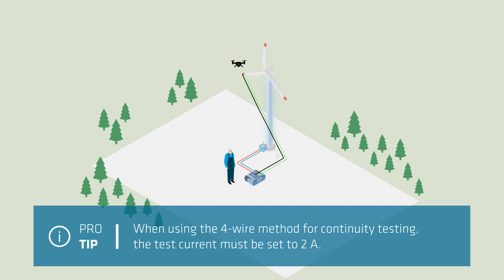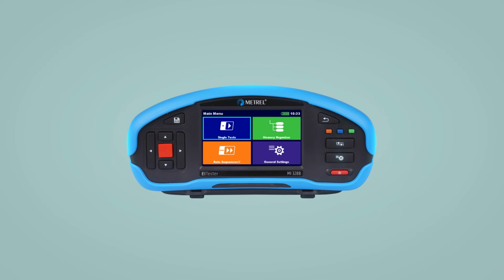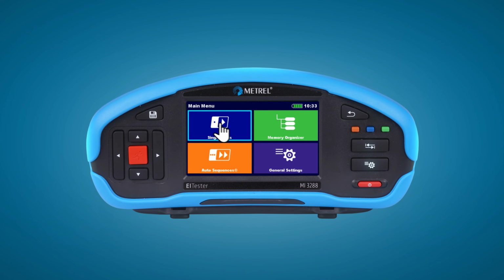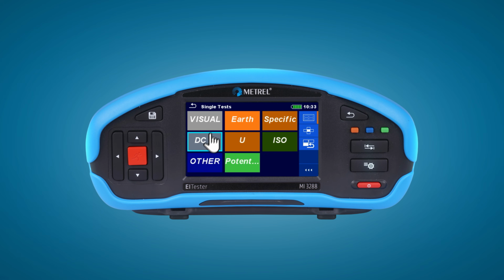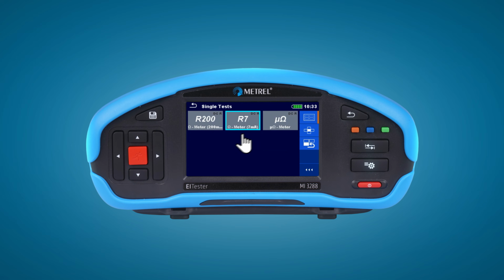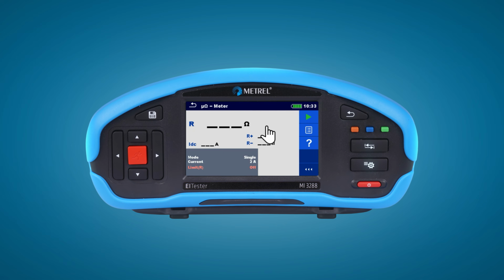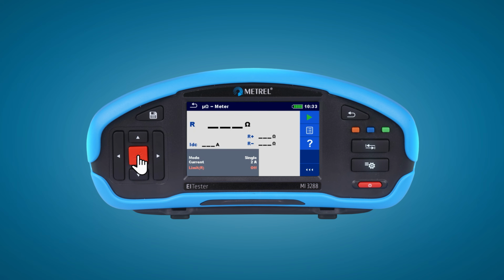The most suitable tool for continuity testing in these situations is the MI3288 tester. Simply select single tests, DC resistance measurements, and micro-ohm measurements. Ensure that you have set the current to 2 amps before starting the test.